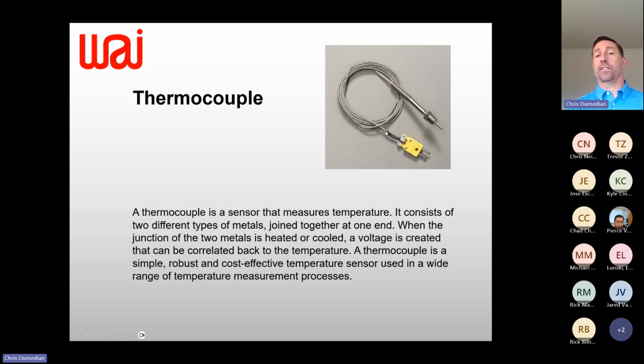The catch with a thermocouple is it's slow to react to temperature changes, which may or may not be okay. Your other trade-offs for that low cost are based on that low voltage output. You have to have a specific material that is calibrated to mate to that sensor here to get back to this device, to make sure that you're getting that voltage output at the thermocouple. And then again, you need a special card to interpret that. So this portion of the picture is very low cost, but you've got some things to be aware of, which is the cable and then interfacing with your PLC, process control, or machine controller. Questions on thermocouples?